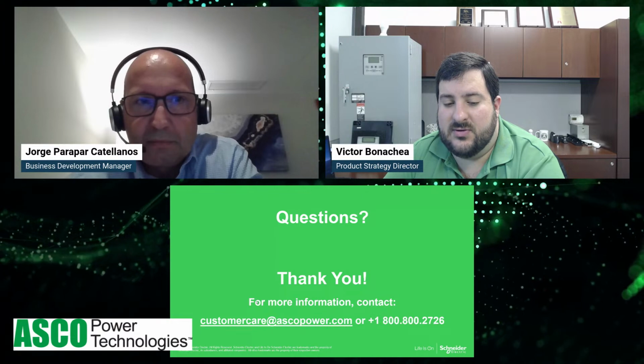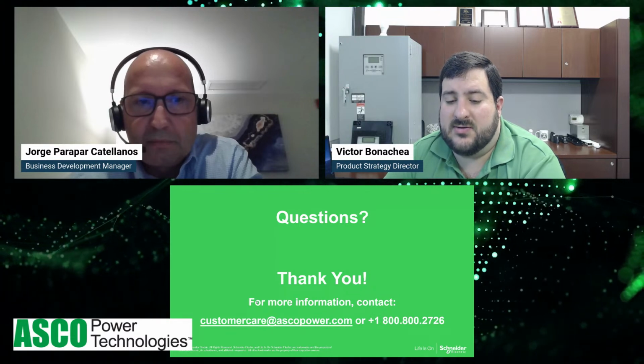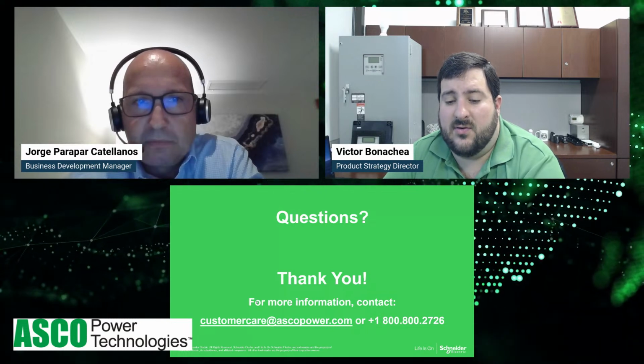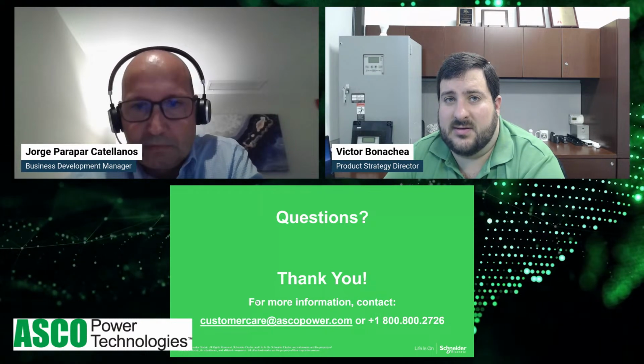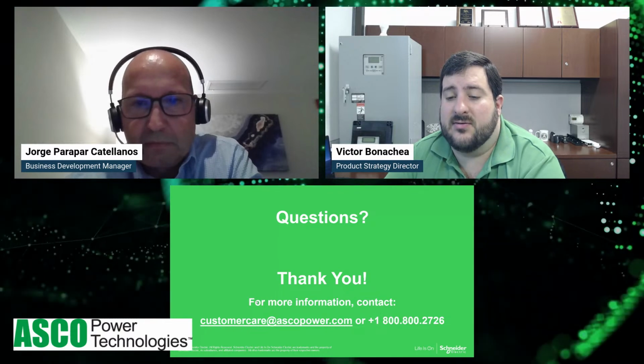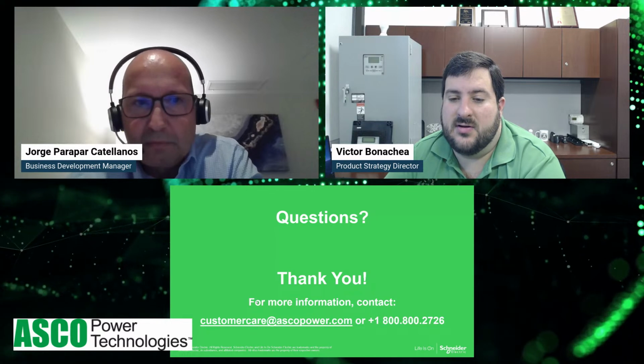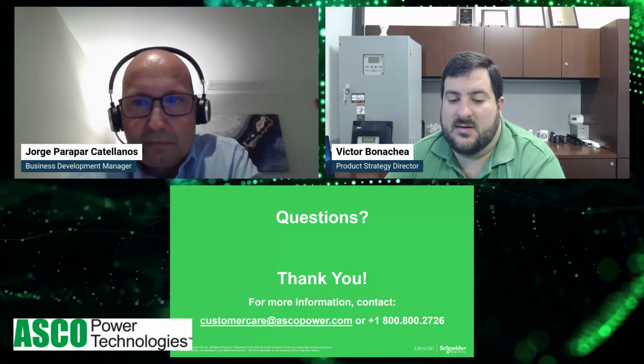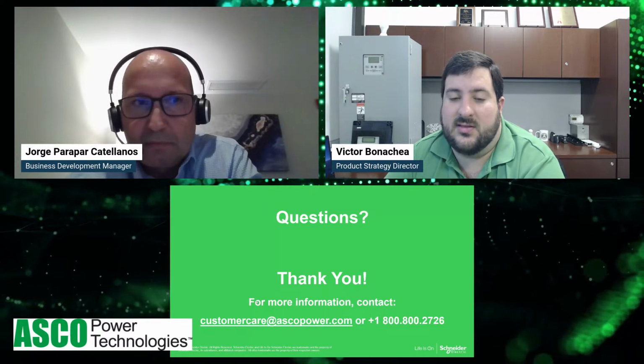Like I mentioned when we spoke about standards, you want to make sure that the withstand rating of the transfer switch is coordinated for where it will be installed in the system and relative to what other circuit breakers and equipment is in the system, so that you don't over or under engineer the transfer switch design or the overall electrical system design.